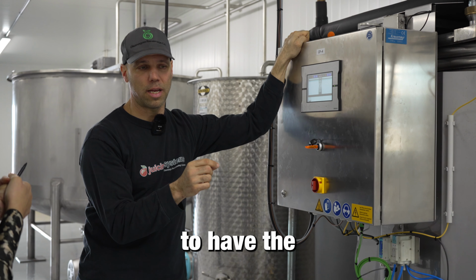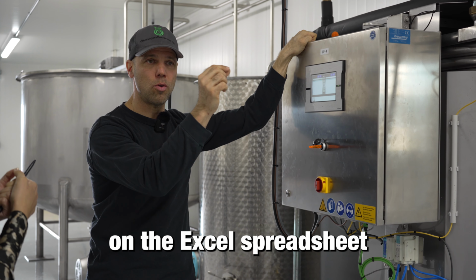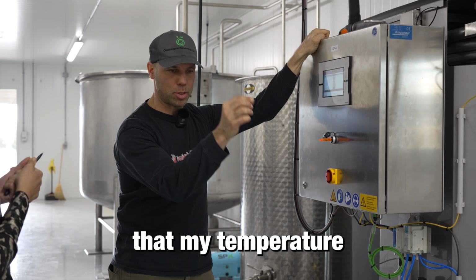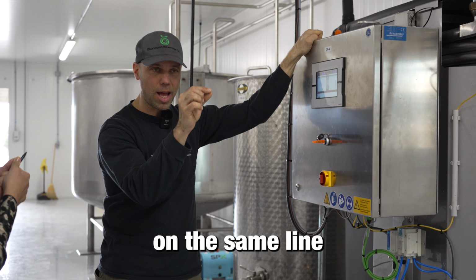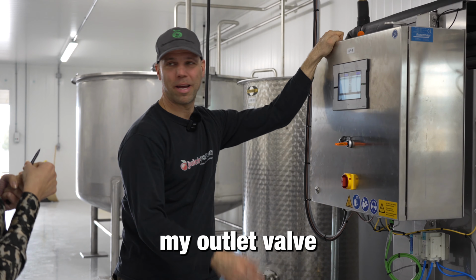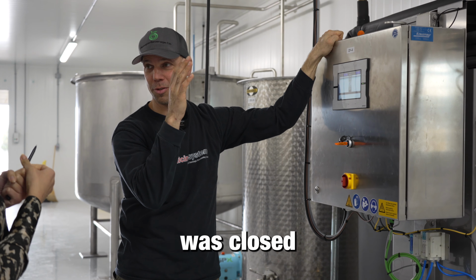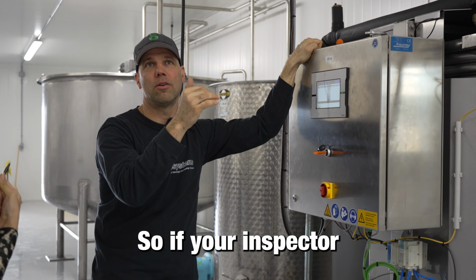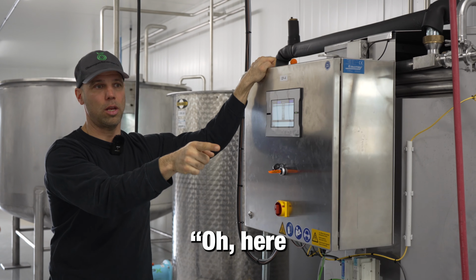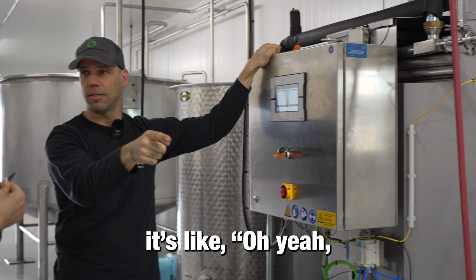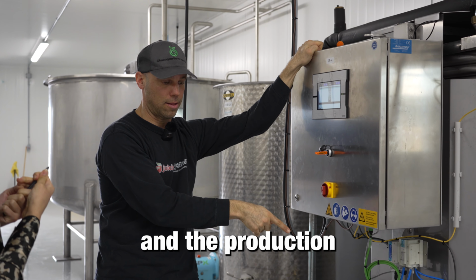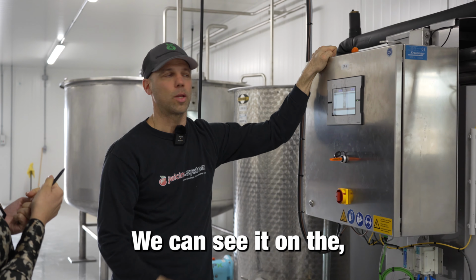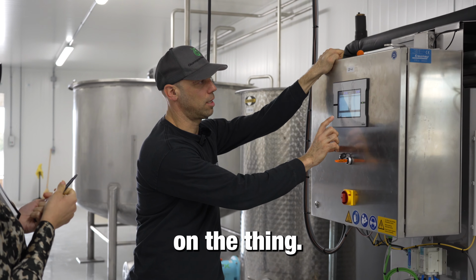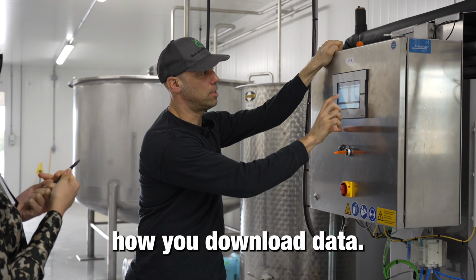So it's important to have the valve position, because if I show on the Excel spreadsheet that my temperature was below, on the same line on the other side, I can show that my outlet valve was closed and my inlet or my back valve was open. I can show that on the graph. So if your inspector comes along and says, oh, here, you want a temperature, it's like, oh, yeah, the back valve was open and the production valve was closed. We can see it on the thing. So that's how you download data.